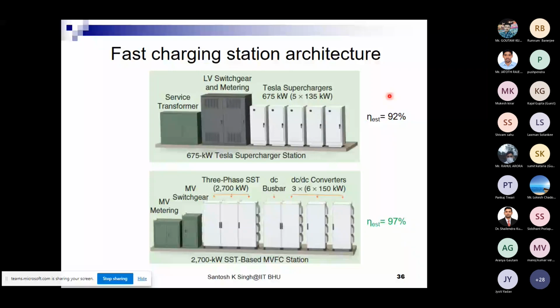And this is our estimated values for a new station. In the bottom one, it is expected that we can have some medium voltage metering, then some switchgear that will certainly be required. But at this level, they are making use of a solid state transformer, a three-phase SST of around 2700 kilowatt.